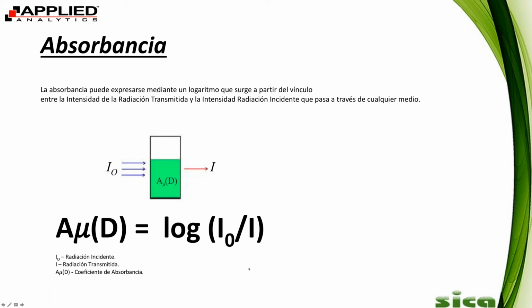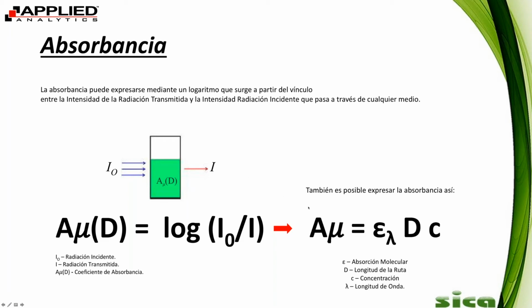So here you can see how the absorption is calculated by using the light intensity going into the sample, the light intensity going out of the sample, and the distance of the flow cell. So it's basically just absorbance is equal to the log of the light intensity going in over the light intensity coming out. And we are able to express this absorption value as a concentration by using this next equation you see here. You can see there's a constant, that's the extinction coefficient. That's a given at each wavelength for each chemical. So that's a given, that's a constant.